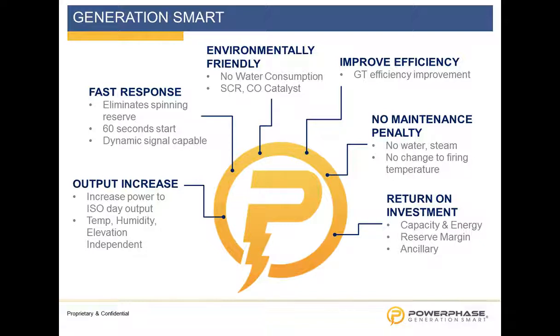And one of the things that comes up is always about the gas turbine maintenance. We make a different amount of megawatts per module per gas turbine based on firing temperature. Right? A B-class gas turbine has a lower firing temperature typically, and pardon for those that think in Celsius, I think in Fahrenheit. Call it a 2055 firing B or E class gas turbine compared to a 2400 firing F class compared to a 2650 firing H class gas turbine. The higher the firing temperature, the more kilowatts per pound per second of air you make. So we make the same amount of air. The higher the firing temperature is, the more kilowatts per pound per second of air you receive out of it.